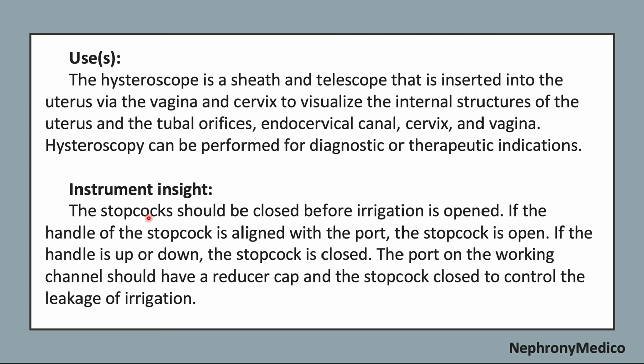The stopcock should be closed before irrigation is opened. If the handle of the stopcock is aligned with the port, the stopcock is opened. If the handle is up or down, the stopcock is closed. The port on the working channel should have a reducer cap and the stopcock closed to control the leakage of irrigation.